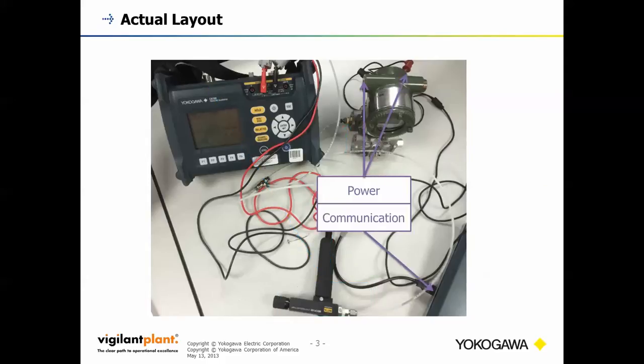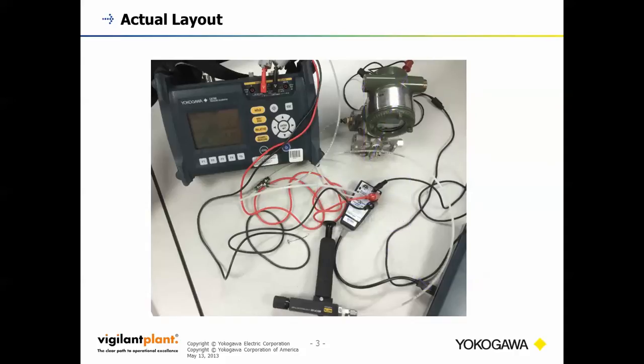These purple arrows are highlighting what the modem is doing. So the top two arrows are showing how the modem is providing power to the transmitter via two IC clips in the back of the transmitter, and then also providing HART communication to the PC via a USB port. The calibrator is getting the milliamp analog signal from the transmitter, and this is showing that. The modem actually provides a couple of clips to show the milliamp output from the transmitter. So the calibrator is taking the milliamp output, analog output from the transmitter, and comparing that against its pressure reading.